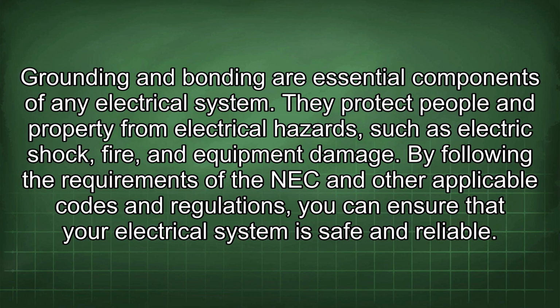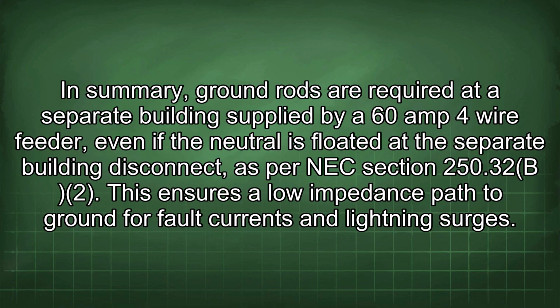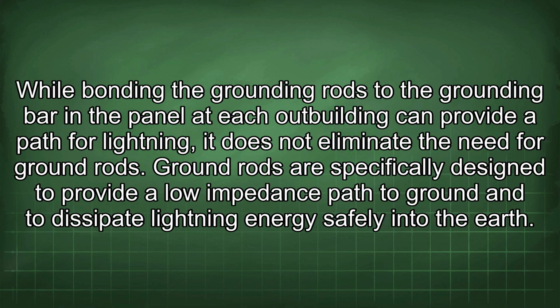is safe and reliable. In summary, ground rods are required at a separate building supplied by a 60 amp 4-wire feeder, even if the neutral is floated to the separate building disconnect, as per NEC section 250.32(B)(2). This ensures a low impedance path to ground for fault currents and lightning surges. While bonding the grounding rods to the grounding bar in the panel at each outbuilding can provide a path for lightning, it does not eliminate the need for ground rods.